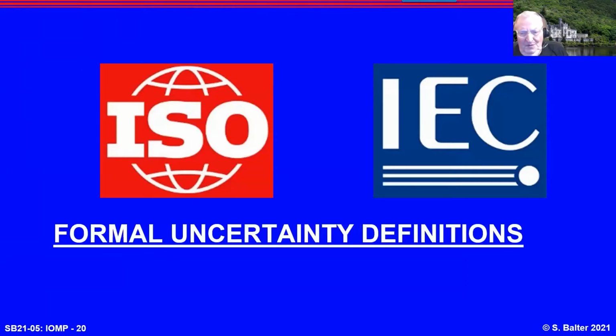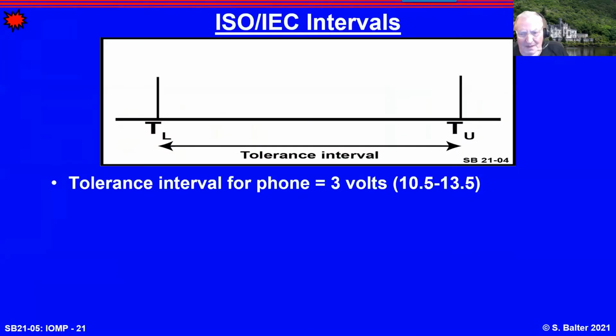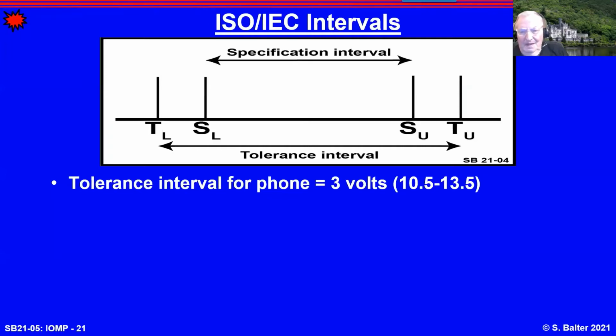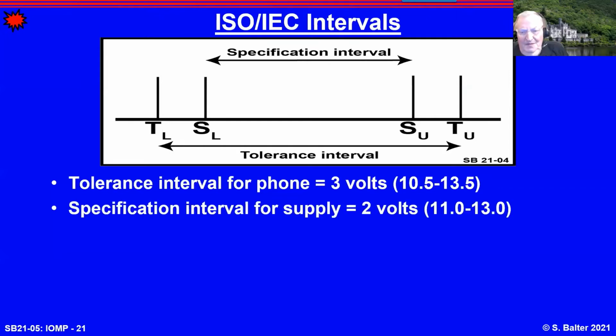So here are formal uncertainty definitions, ISO, IEC, which in this area actually work together, and many of these documents are joint documents. We start with the tolerance interval, and again, this is formal language in ISO IEC. For the phone example, the tolerance interval was 3 volts between 10.5 and 13.5 volts. This power supply was specified as 11 to 13 to allow a safety margin.